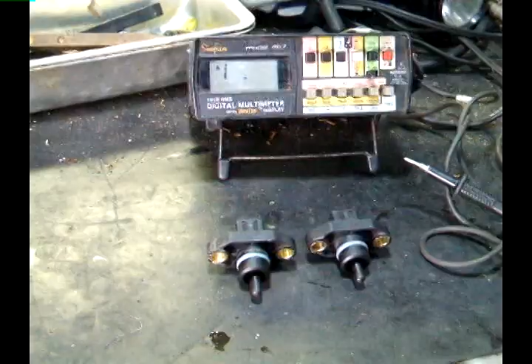So after you have the sensor removed, I'm going to show you how to test a good one and a bad one. Set your volt ohm meter to ohms on the 20K scale. Terminals doesn't matter, you just test the resistance across.